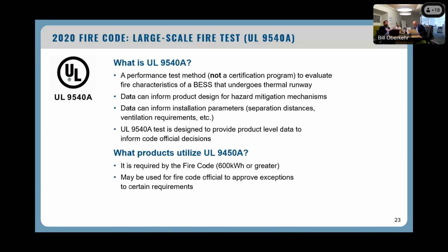So the last one was UL 9540, and that's typically the first thing people encounter when they start looking at 9540A. That was a listing, a stamp of approval. There's no room for interpretation. You either have that equipment listing or you don't. It's binary. UL 9540A is not like that at all. It's not a listing.